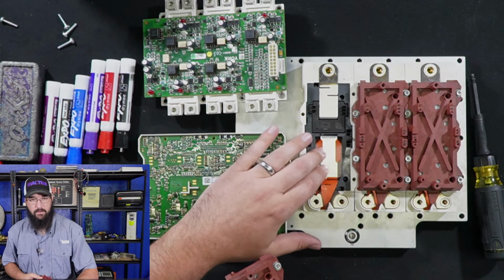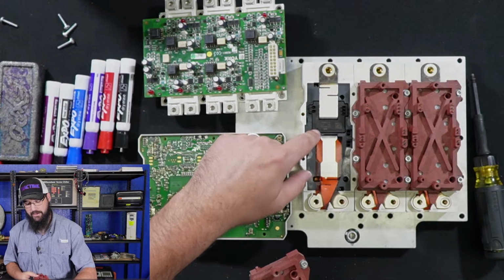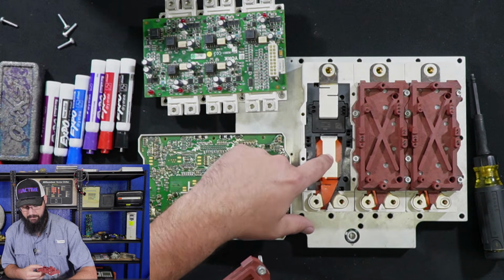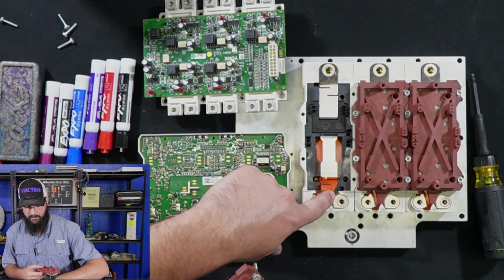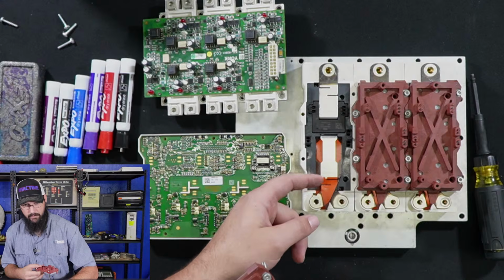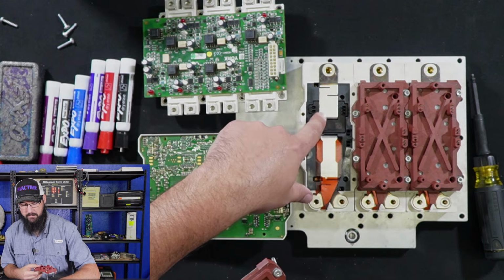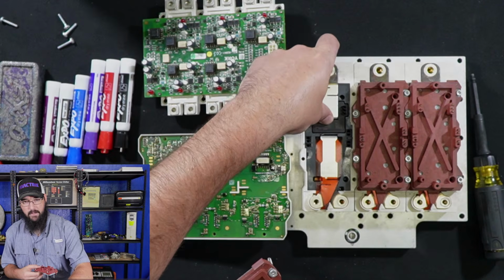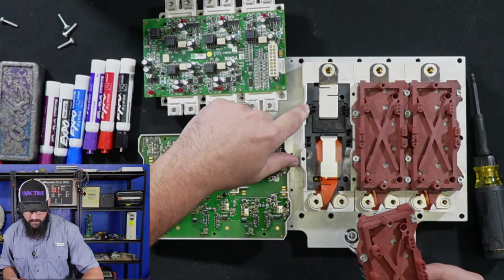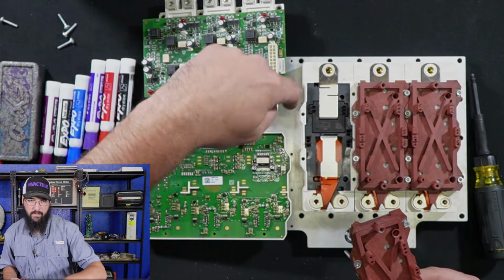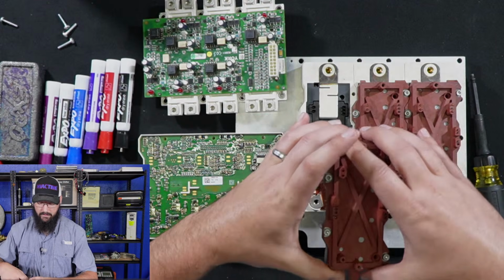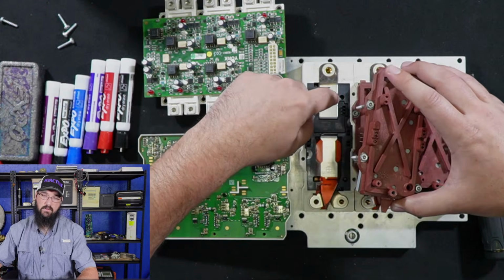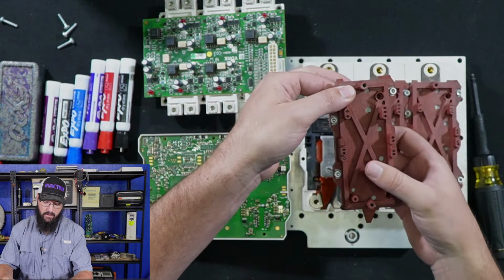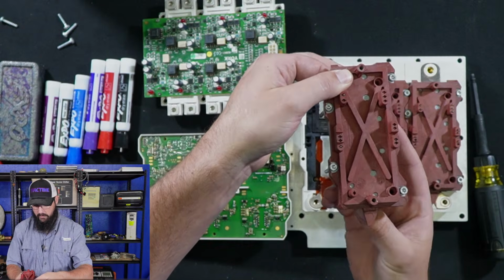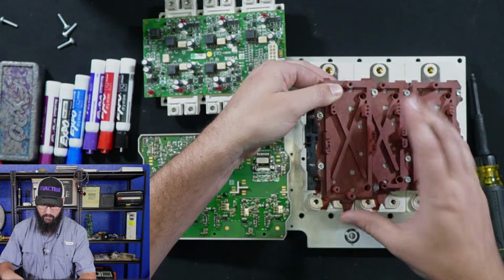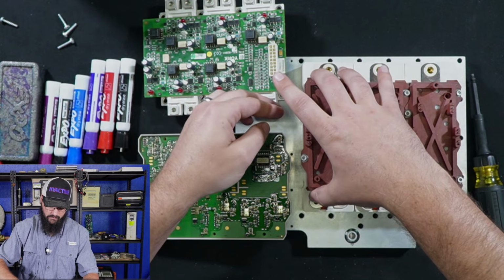But you can see this is your actual IGBT transistor here. And we have our positive coming in. There is still insulation here between the positive and the negative. That's what this lamination paper is. And then we come out of our IGBT module and into our actual output here, the output bus terminal. And then these are those little pinpoints that go down and make contact with the IGBT assembly, or the gates themselves. You could think of a gate like a coil for a contactor. So we're going to energize a gate in order to activate the transistor.